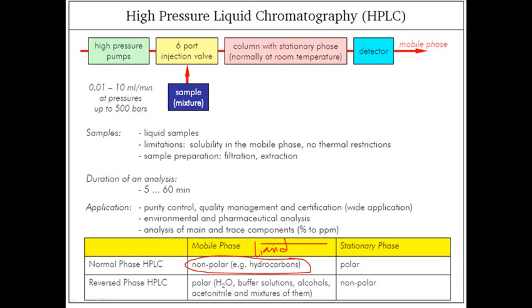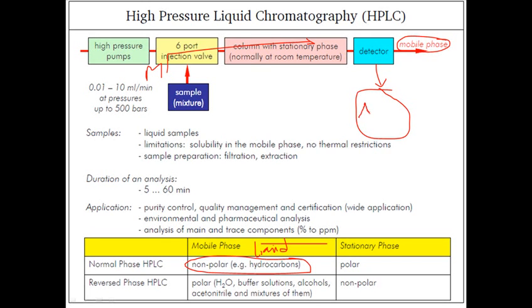In this setup, we have a high pressure pump through which pressure is created. You inject the sample into the six-port injection valve, and the sample is carried by this pressure via the mobile phase molecules from one end toward the detector. The detector detects it, feeds the data into a computer screen, and an elution is done with further mobile phase, finally producing a chromatogram.